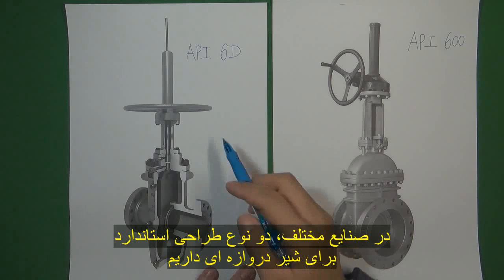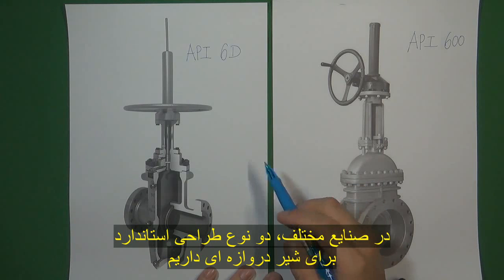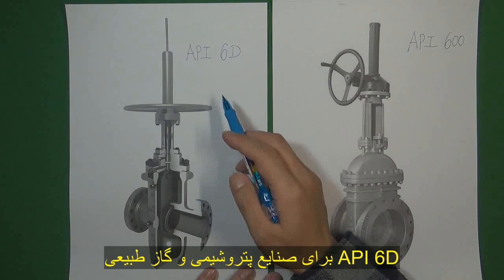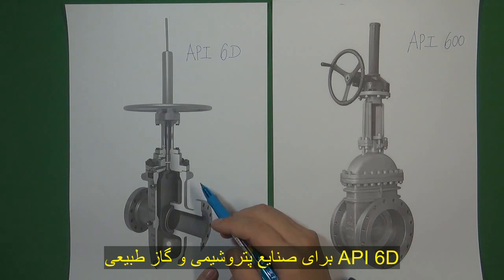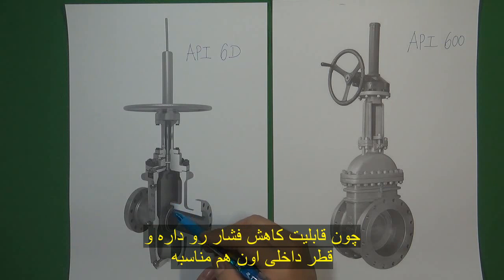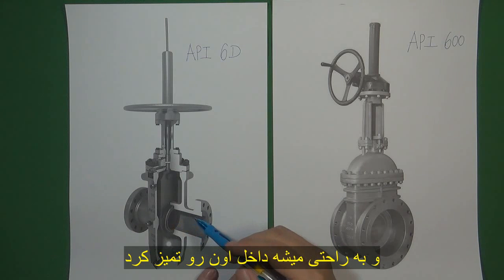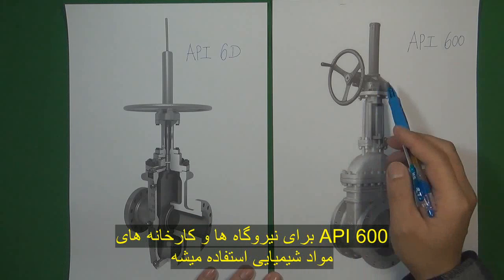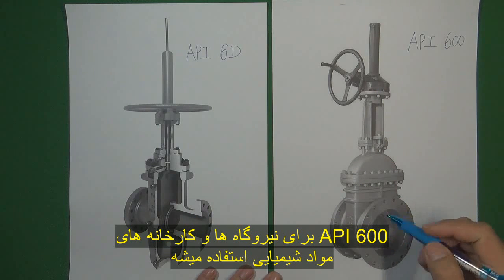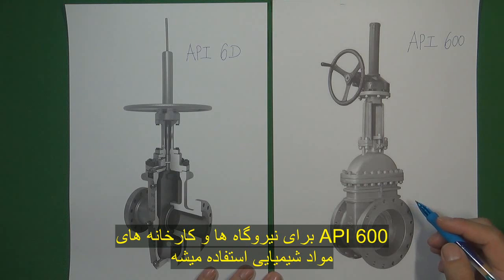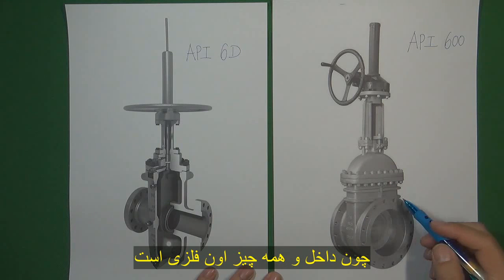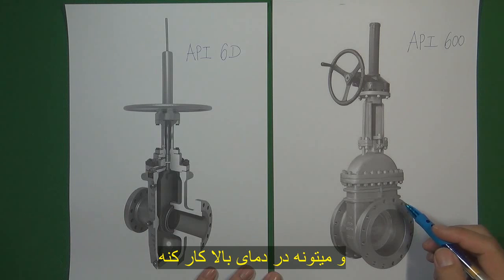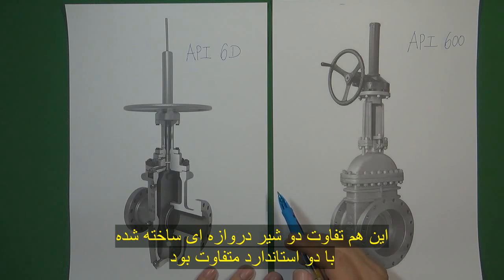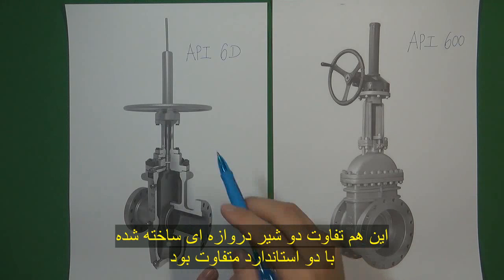According to the different designs, the two kinds of standard design two kinds of gate valve working in different industries. API 6D is for valves that work in the petroleum and natural gas industry because the valve has the pressure relief function and also has enough inside diameter for pigging to clean the pipe inside. The API 600 is a gate valve designed for the power plant and the chemical plant because inside the valve everything is made of metal. It can work in a very high temperature environment. So those are the several basic differences between the two kinds of gate valve designed by the two kinds of standard.